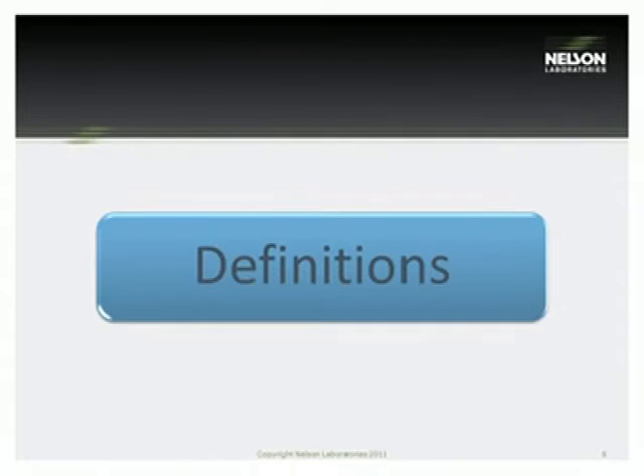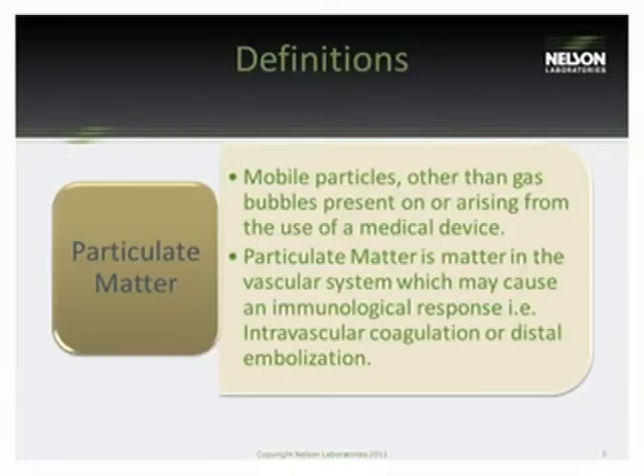Now, some basic definitions that we may use throughout the presentation that are commonly used in particulate matter testing. First, particulate matter, by definition, is regarded as mobile particles other than gas bubbles that are present on or arising from the use of a medical device or liquid. Particulate matter is matter in the vascular system which may cause an immunological response or intravascular coagulation or distal embolization.